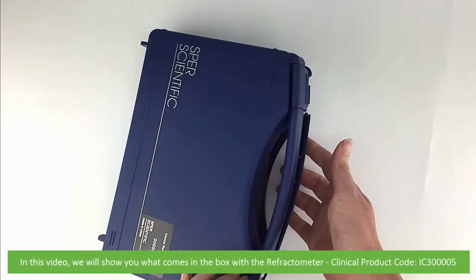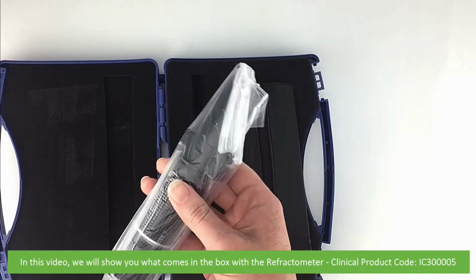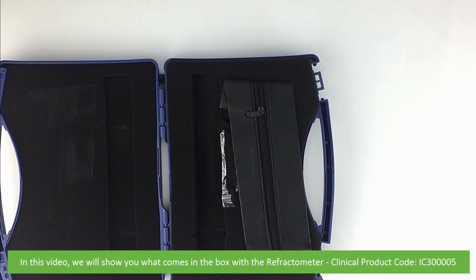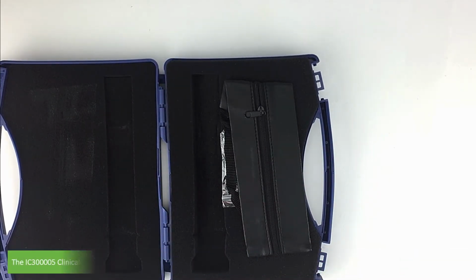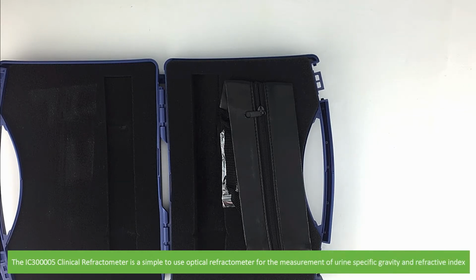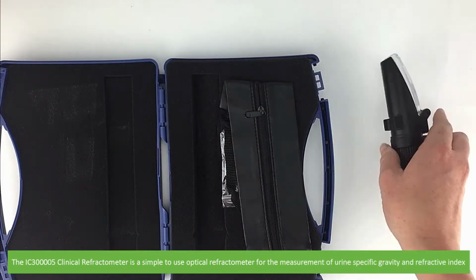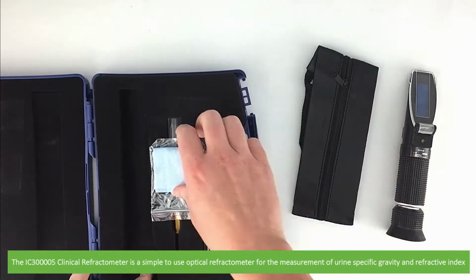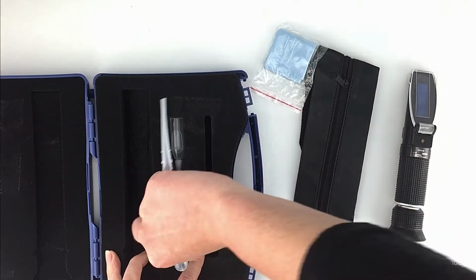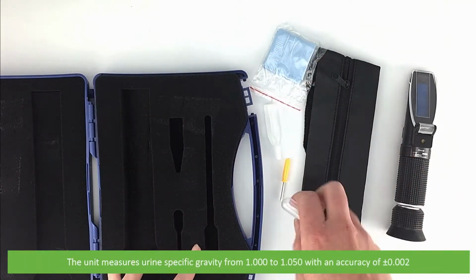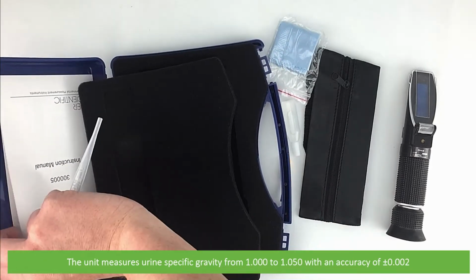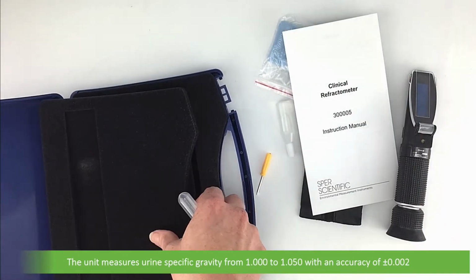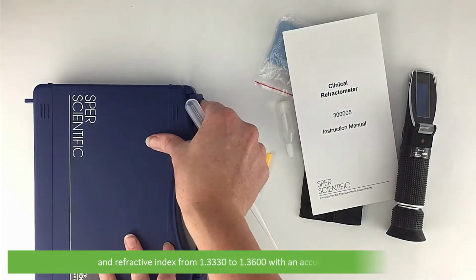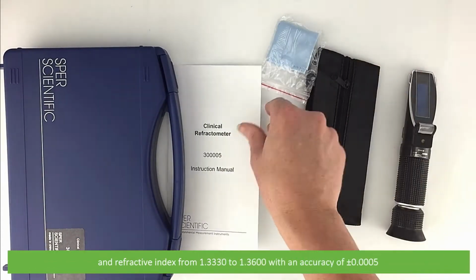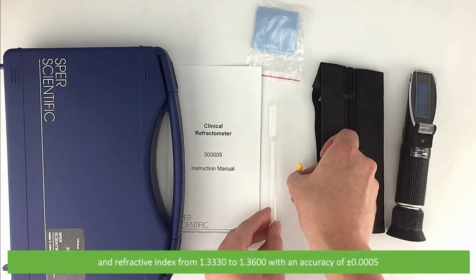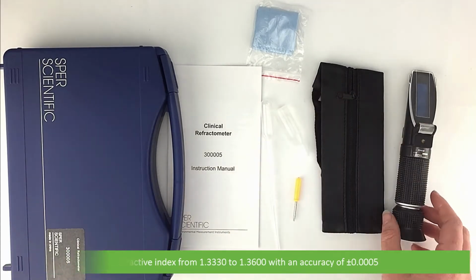In this video we'll show you what comes in the box with the Refractometer Clinical. The product code is IC300005. The IC300005 Clinical Refractometer is a simple to use optical refractometer for the measurement of urine specific gravity and refractive index. The unit measures urine specific gravity from 1 to 1.05 with an accuracy of plus or minus 0.002, and refractive index from 1.333 to 1.36 with an accuracy of plus or minus 0.0005.